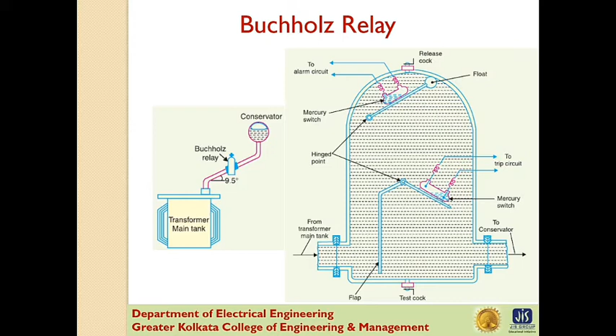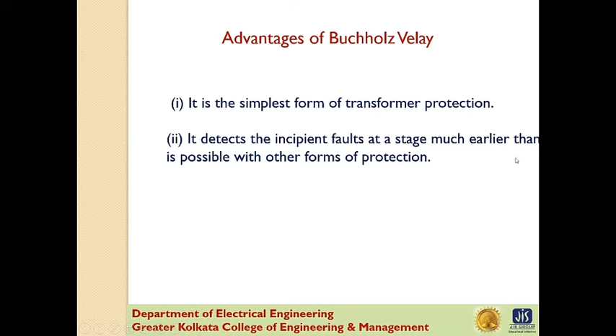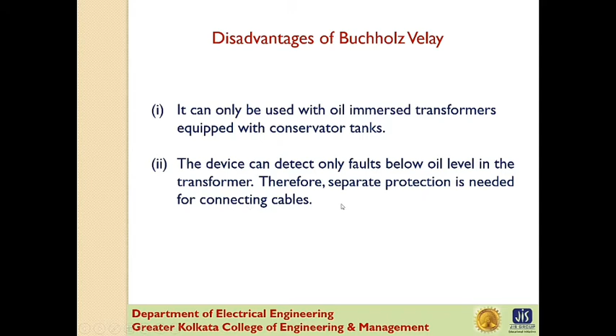Now, what are the advantages of the Buchholz relay? First, it is the simplest form of transformer protection. Next, it detects incipient faults at a stage much earlier than is possible with other types of protection. Now, a disadvantage of the Buchholz relay: it can only be used with oil-immersed transformers equipped with a conservator tank. The device can detect faults only below the oil level in the transformer. Therefore, separate protection is needed for connecting cables.